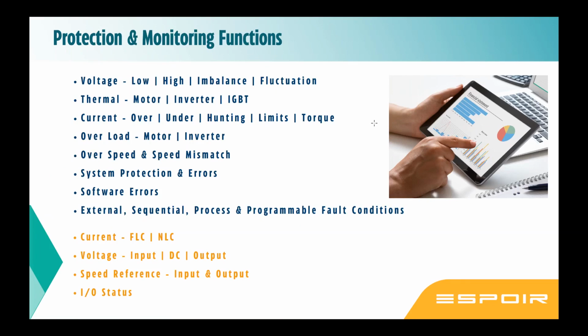Overspeed and speed mismatch. You can achieve this only when you have a feedback system, meaning you need a closed loop system. You need to have an encoder. You need to set the limits. Then it can protect you from overspeed and speed mismatch. Particularly in a test bench, these features are very usable. In a hoist system, overspeed you need to protect against. Otherwise it is considered a free fall, meaning a brake failure or some other issue. So you need to protect the system.